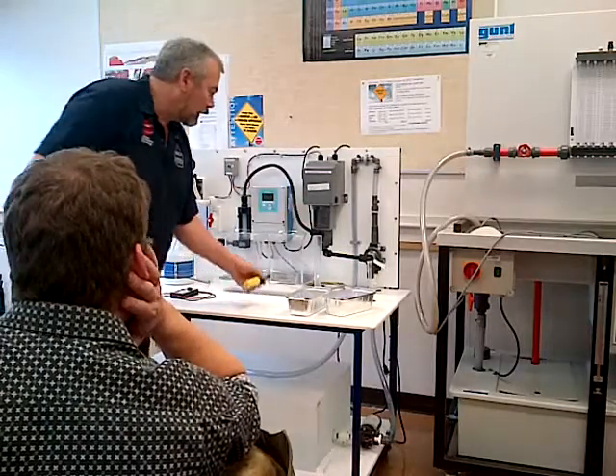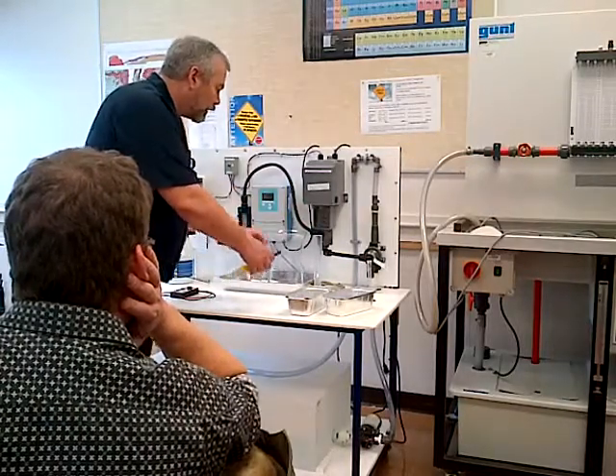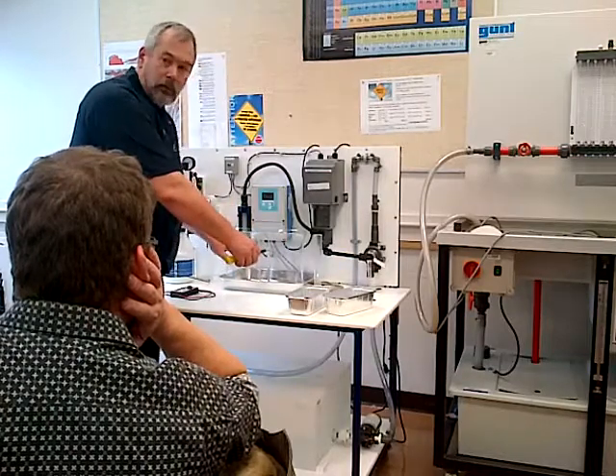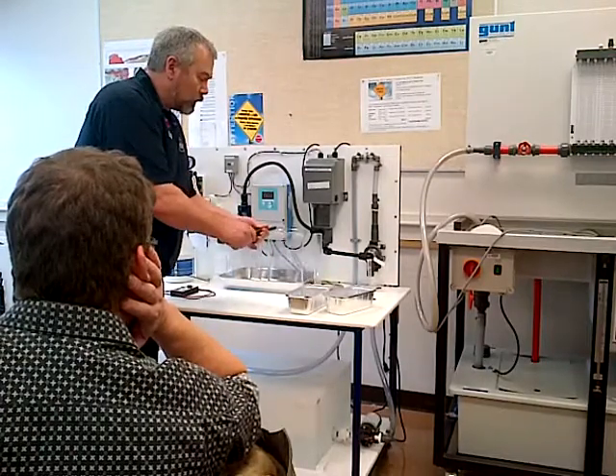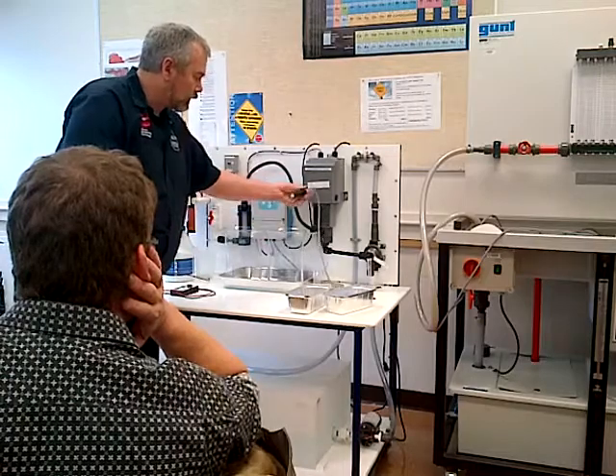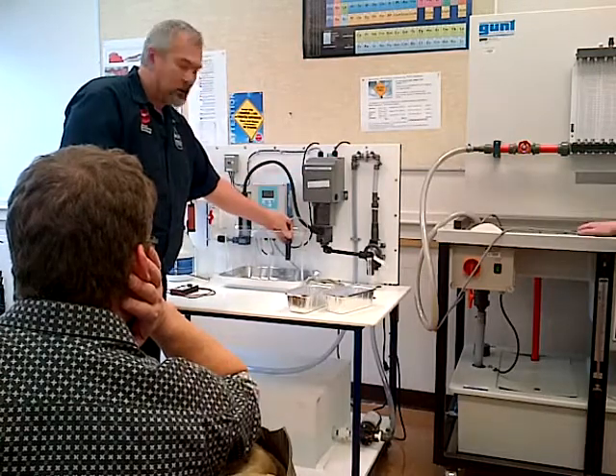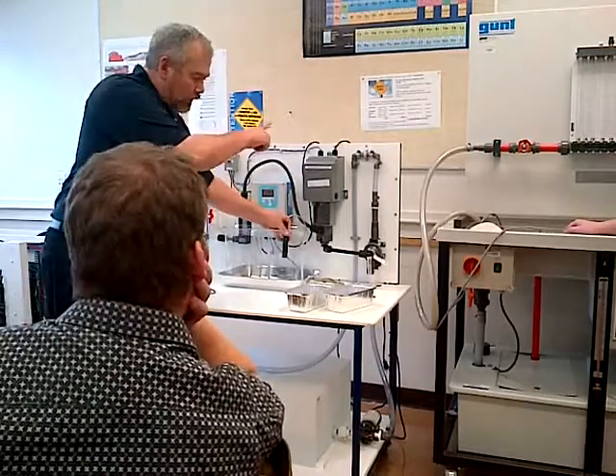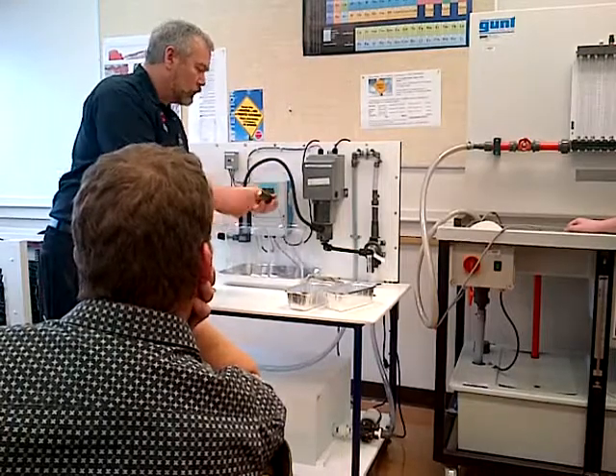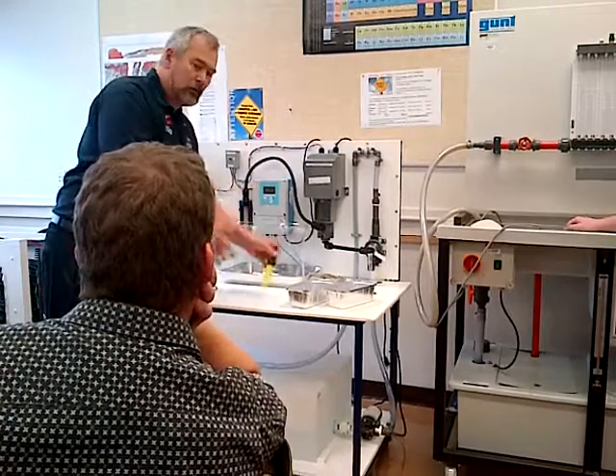So we can simulate like pouring water and bleach. So we'll just have one container with clean water, one container with a bit of bleach. We're going to test it. We're going to actually dip the probe inside, and you'll see the valve open and close. Rinse it off again, please, and put it back.